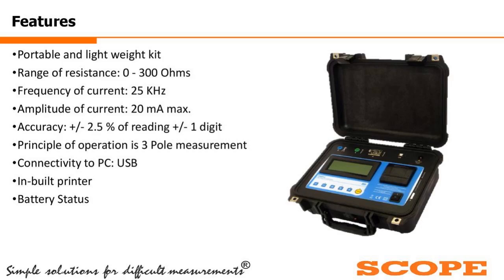Now coming to the product, it is a portable and lightweight kit. Range of resistance measurement is up to 300 ohms. Frequency of test current is 25 kilohertz. Amplitude of current is 20 milliampere maximum; it depends upon the effective resistance. So it can go up to 20 milliampere. Accuracy is plus minus 2.5% of the reading, plus minus 1 digit.